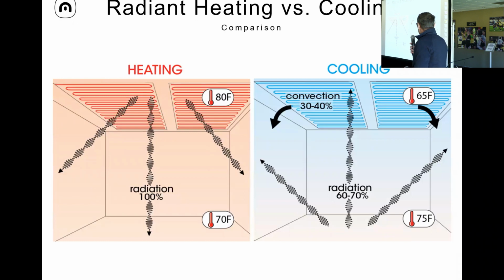In this slide, we are comparing using a radiant ceiling as a radiant terminal, comparing heating versus cooling. As I mentioned before, when we do radiant ceiling cooling, there is always about a 30 to 40% component that is convection, cold air flowing down, and that helps the ceiling absorb the heat, making the ceiling more efficient.